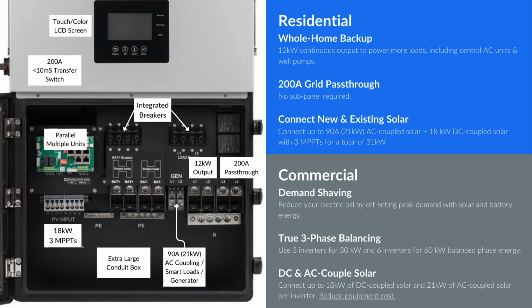Moving on now to the Luxpower 12K inverter. This is really a Swiss Army knife hybrid inverter that we use for residential and light commercial. Some of the features that this inverter offers: a color touch LCD screen, which makes programming and monitoring very simple. There's an integrated 200 amp transfer switch, less than 10 milliseconds. You can parallel multiple units together for larger power outputs.